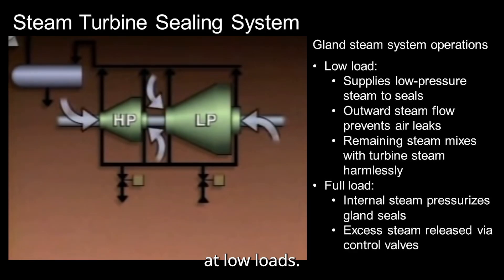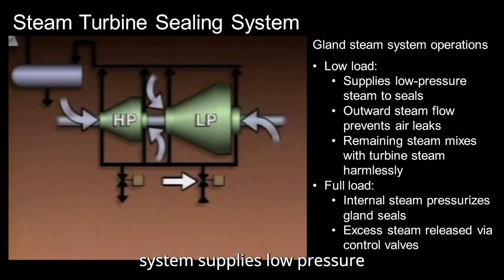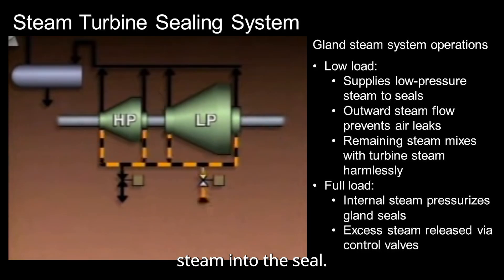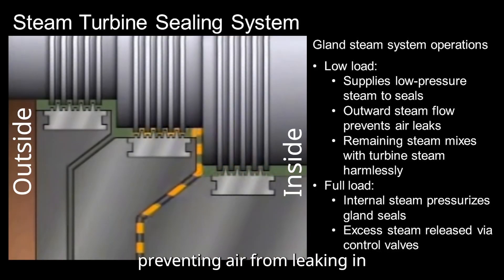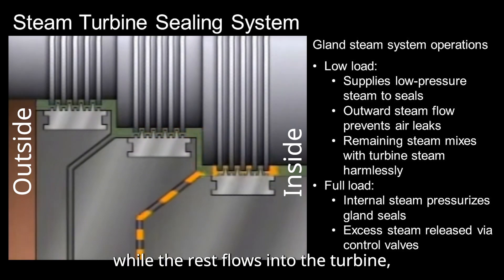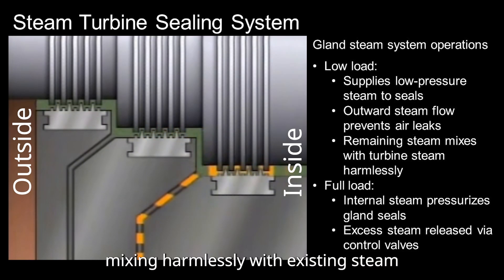Let's see how these systems work together to maintain efficiency and safety. At low loads, when the turbine is under vacuum, the gland steam system supplies low-pressure steam into the seal. Some steam flows outward, preventing air from leaking in, while the rest flows into the turbine, mixing harmlessly with existing steam.